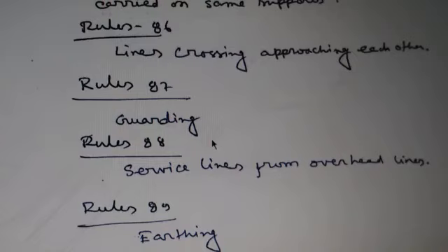Next point, when there are two trolley wires and the distance between them does not cross 0.381 meters, two guard wires shall be erected. Next point, where there are two trolley wires and the distance between them crosses 0.381 meters, that means 15 inches, but does not cross 1.219 meters, that means 48 inches, three guard wires shall be provided.